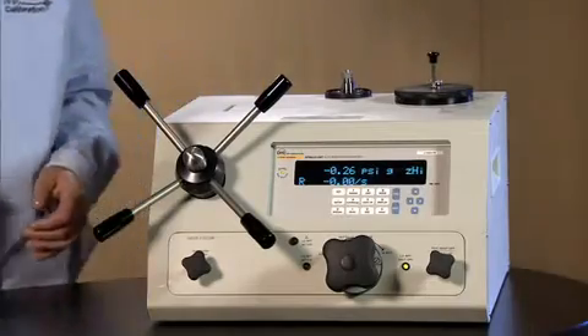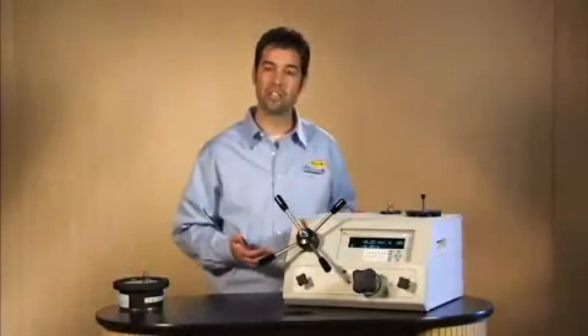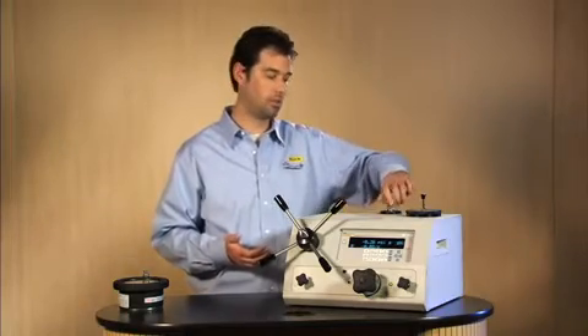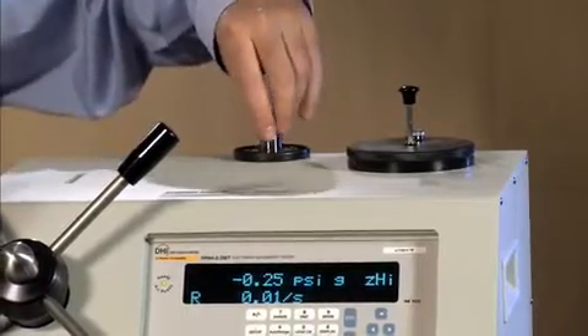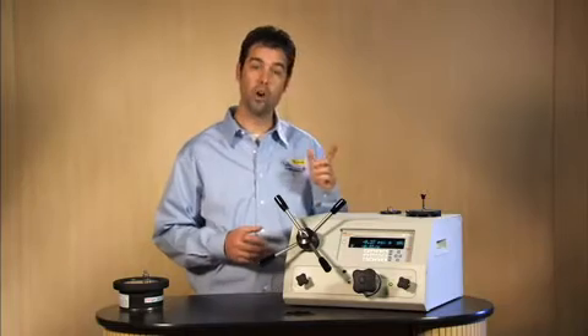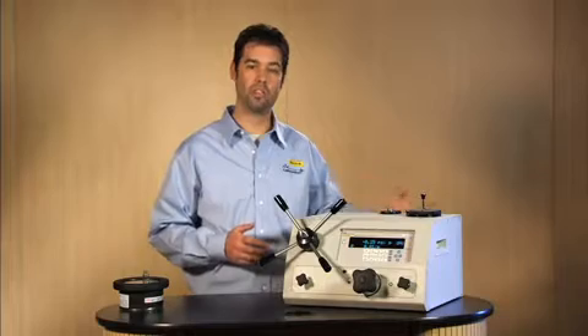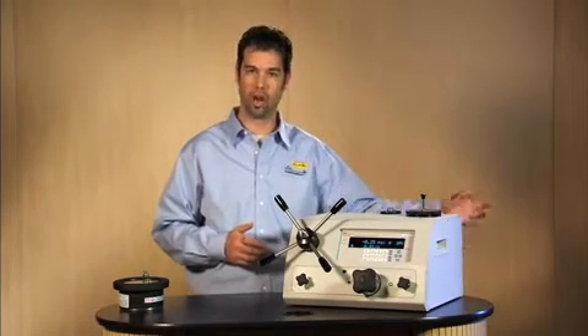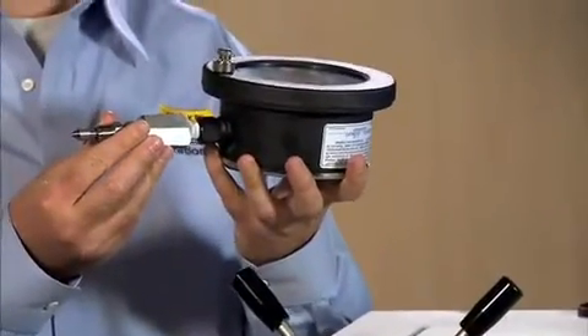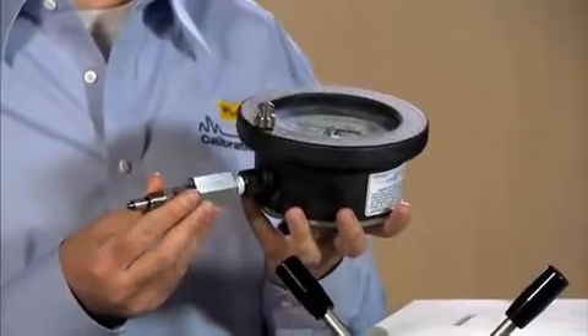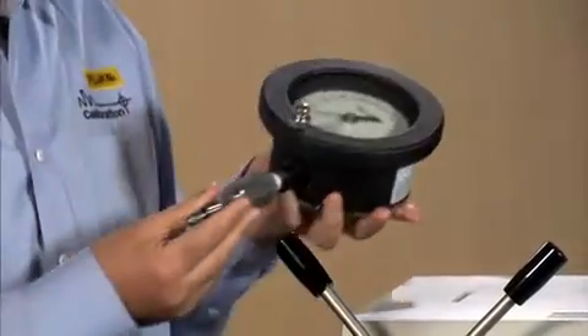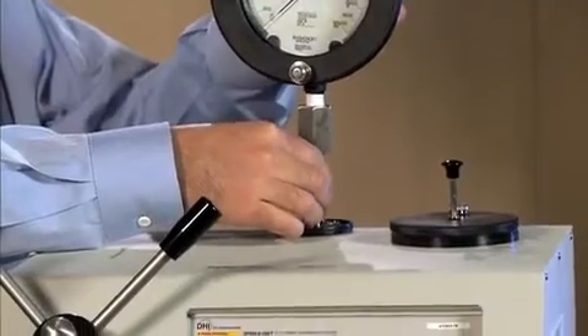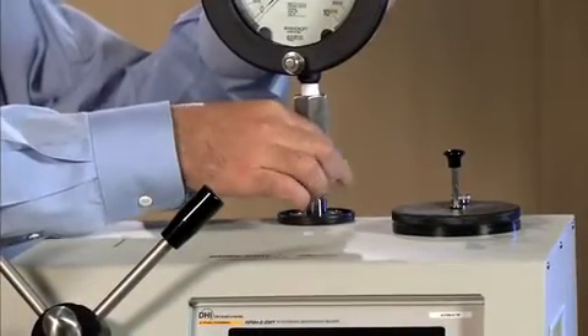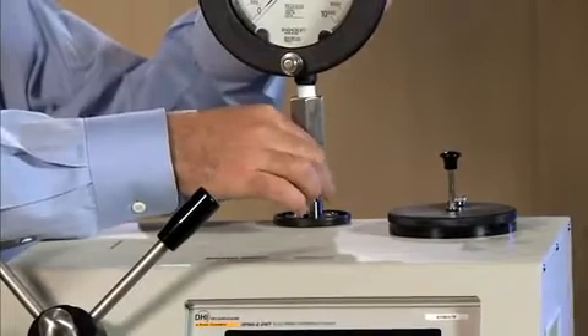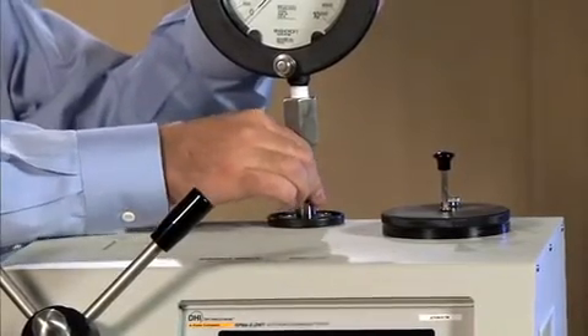Now we are ready to attach our gauge. To attach the gauge, we want to open the plug on the test port of the electronic deadweight tester. Note that there is also a test port on the back of the electronic deadweight tester to be used for other devices. We have already attached the correct adapter to the 10,000 psi gauge and simply place it on top of the deadweight tester and have it a little less than finger tight.